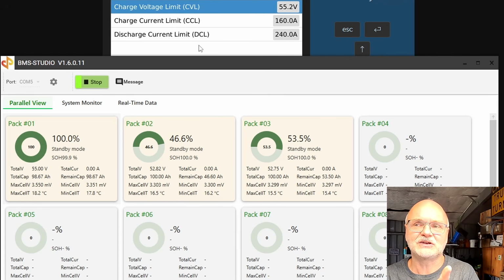So keep charging, but limited to 160 amps. This is the maximum these 2 BMSs, or these 2 batteries, can cope with. While discharging, all 3 batteries take part, so we have 3 times 80 amps, 240 amps maximum discharge current for this whole tower.